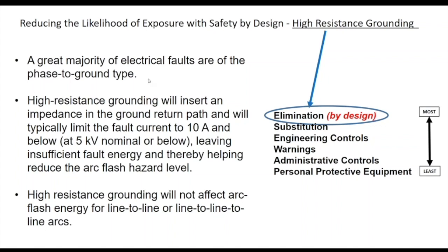But it almost always starts as a phase to ground, often by an uninsulated tool. Our friends in the high voltage world, the linemen, have used insulated tools for a long time, and it's something that's become far more important in the industrial commercial world, but there are still some that don't. High resistance grounding will insert an impedance or a resistance in the ground return path and will typically limit the fault current to 10 amps and below, and that's at 5 kV nominal or below.